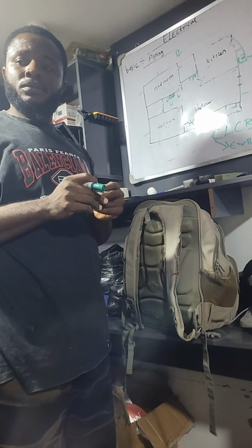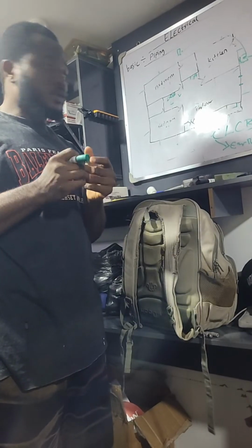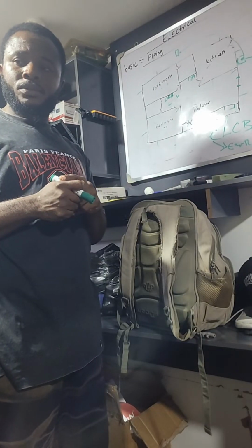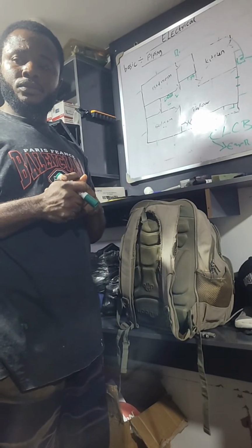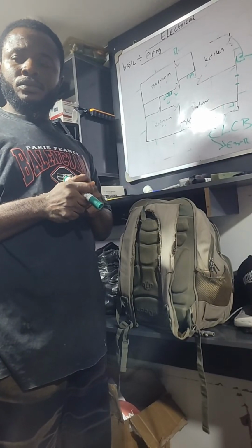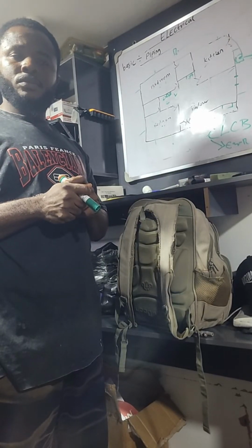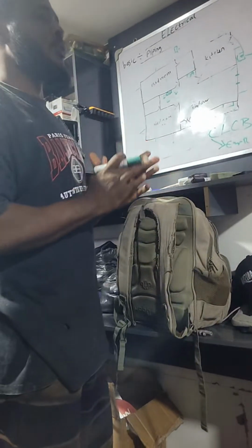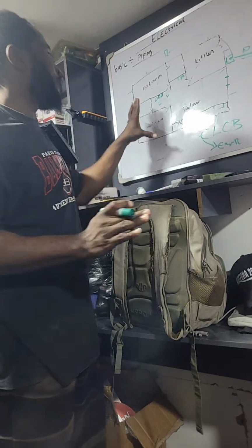For this 2-bedroom, we'll give it 3. Okay, why do you say 3? Because I'm planning to use LED lights that consume less. And the parlor on 1 circuit, the 2 bedrooms on 1 circuit, and the kitchen and outside lights. A lot of applause for him. Good. 2 to 3 is right for this 2-bedroom.